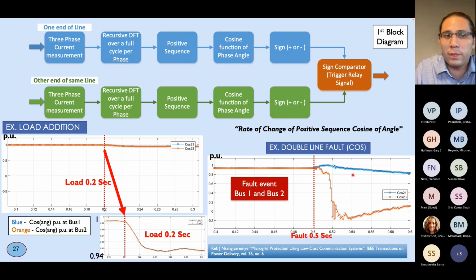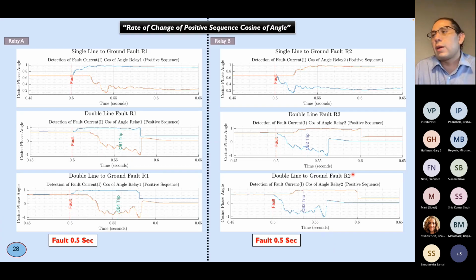I won't explain too much here due to the time constraint, but the method we call the rate of change of positive sequence cosine of angle. And in this figure, I'm showing two different relays' points of view. Like in the distribution line, we measure from two different ends. So we are detecting from each end how each relay, or each device, is seeing the fault within the grid. So we can see that when we have a single line to ground fault, we see a disturbance, and the fault can be detected.